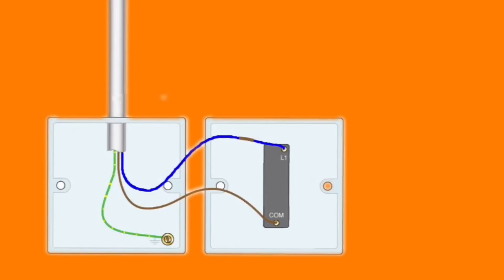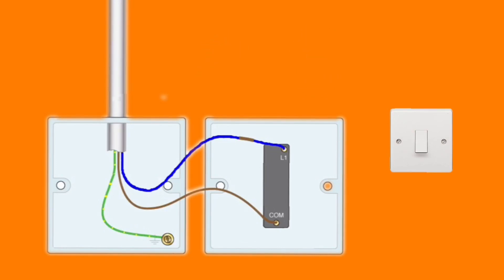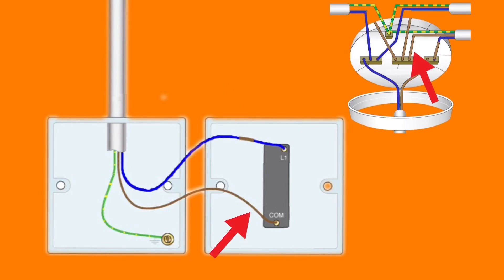In this video presentation we're going to look at the connections for converting a one-way lighting circuit - where one switch turns a light on and off - to have control via two positions by converting it to two-way switching. The current switch drop from the ceiling rose is in blue, brown, and green and yellow, so we've got twin and CPC cable. The blue is not a neutral; it's a switching line conductor identified with brown sleeving at both ends, and we bring down a permanent line connection on the brown conductor connected in common.